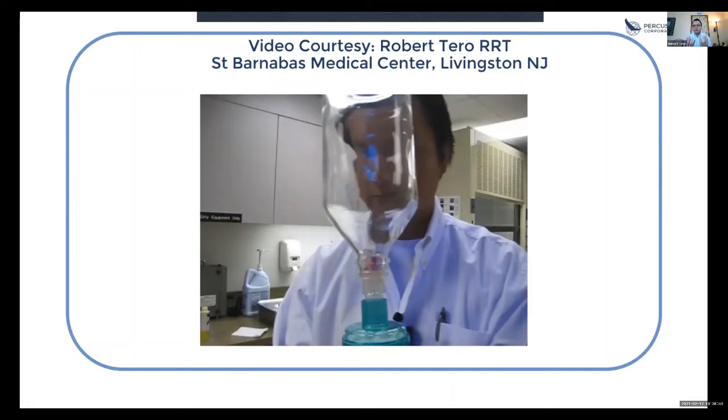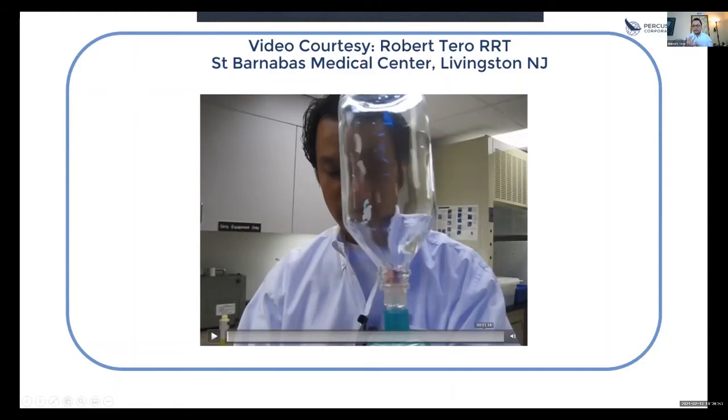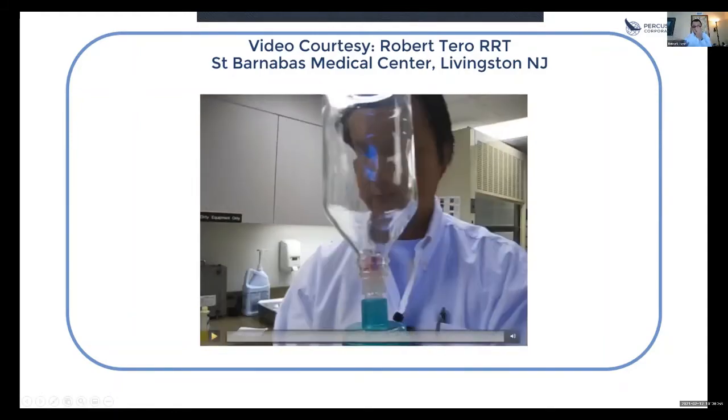We're looking at flow-based and pressure-based ventilation, and why, when you get stuck and you're not really moving forward with pressure-based or volume-based ventilation, maybe it's time to consider percussive-based or flow-based ventilation, so you can penetrate those areas of the lungs that are otherwise extremely difficult to ventilate with those modes. I believe you had a chart you wanted to show about how you approach the waveforms with the VDR.